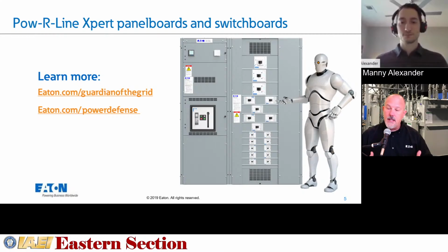Now, what I've been telling everybody is to do both of these tests at the same time. If you're testing GFPE at 1000 amps and above and you're doing primary current injection testing, you can test that arc reduction maintenance switch because it has a very low setting. You have two and a half times or 2 times the rating of that device. So if you have a 1200 amp, all you need is 2400 amps to trip that device, and more often than not, you're going to have the equipment to do that. But we do have methods to do that testing separately as well. So just be mindful of that.